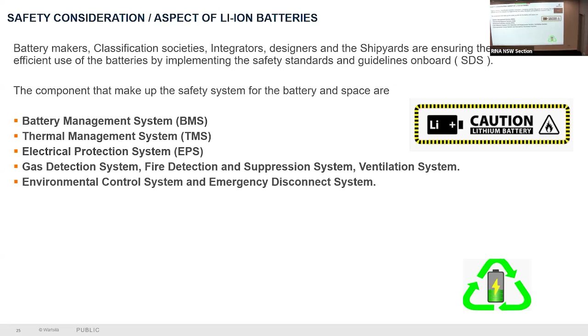Now I want to give you an example here. What are the common hazards when we talk about battery safety? Thermal runaway is one very important thing. Another is a sudden rise in voltage, which can damage the electronic devices on board. Thermal runaway is nothing but: if current is passing through the cell, there is a rise in temperature, which further raises the current in the system, which further raises the temperature, and which can lead to fire. Now, if there is a fire, since these are liquid state batteries, the electrolyte can leak, converting into toxic gases with toxic compounds. So we need a gas detection system.